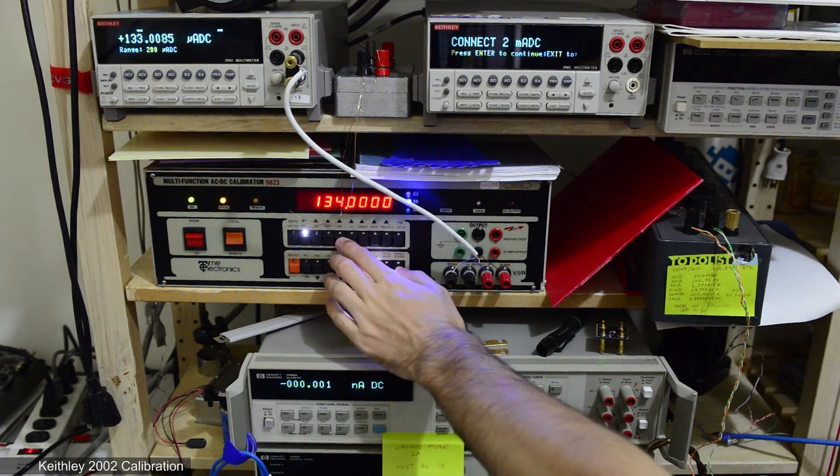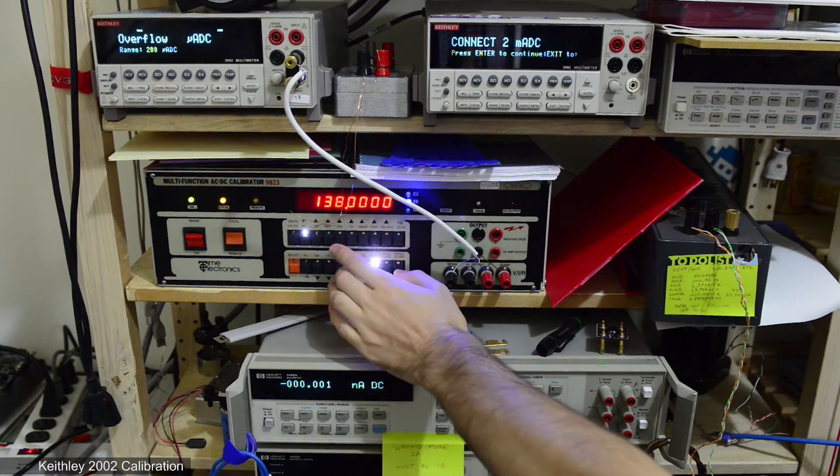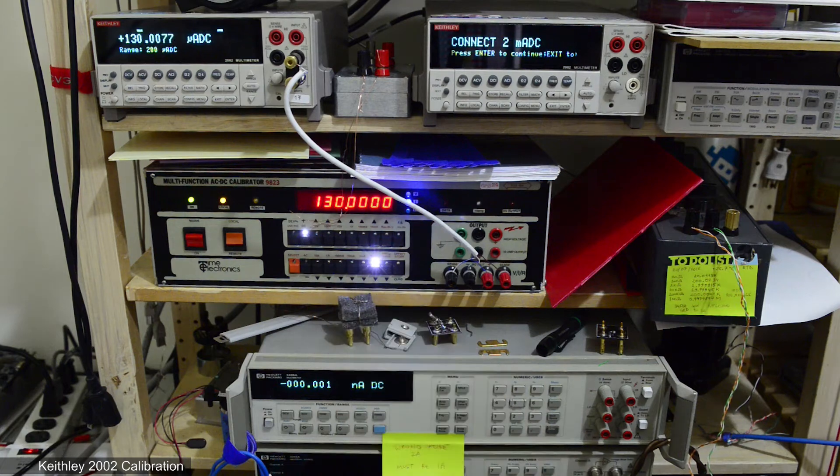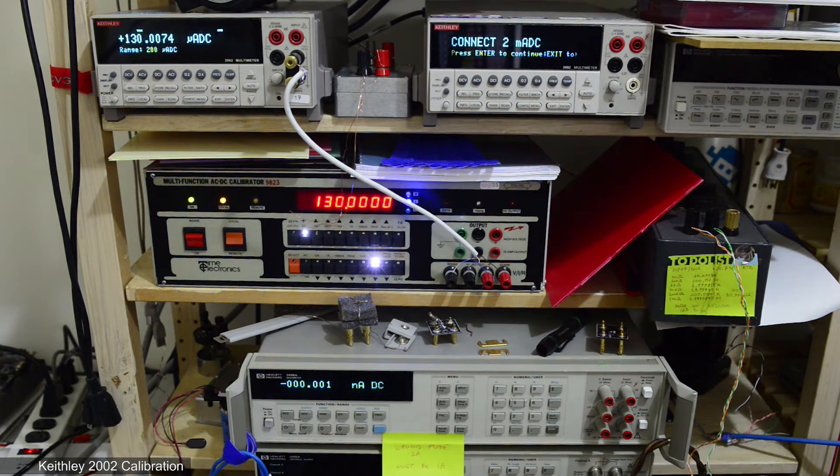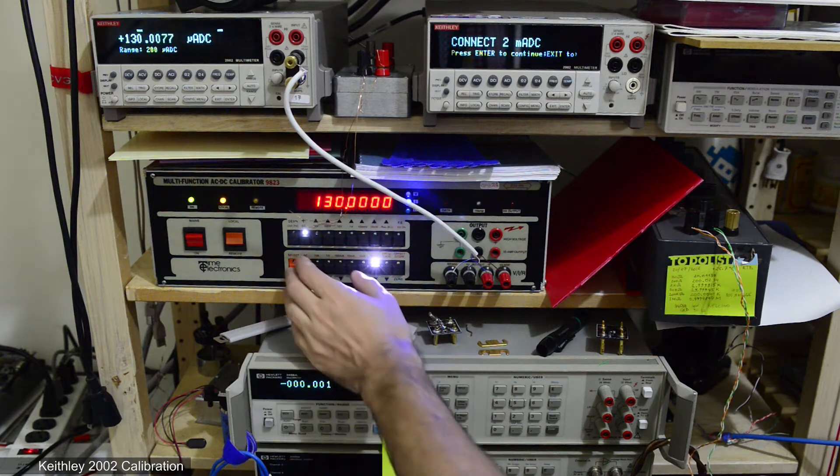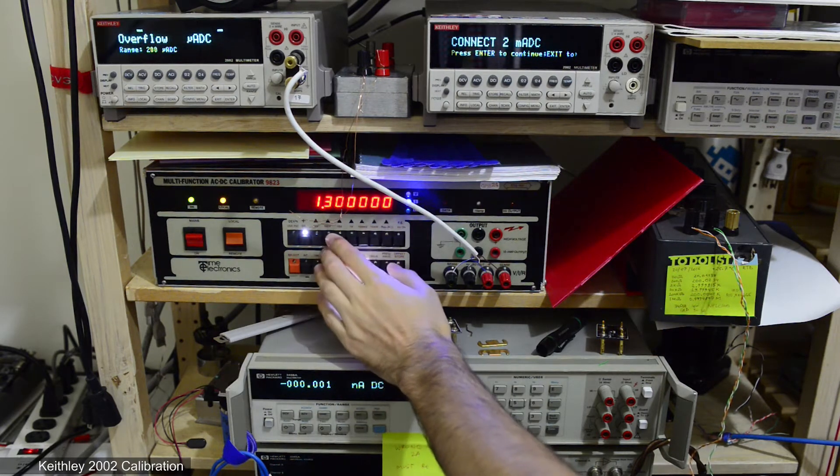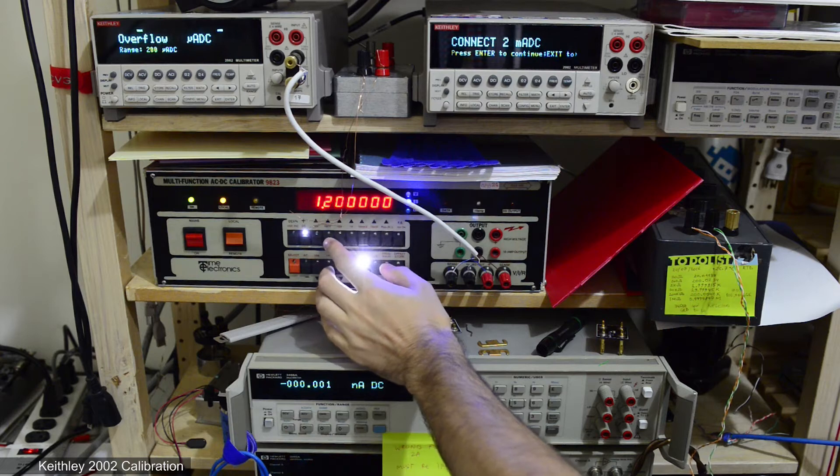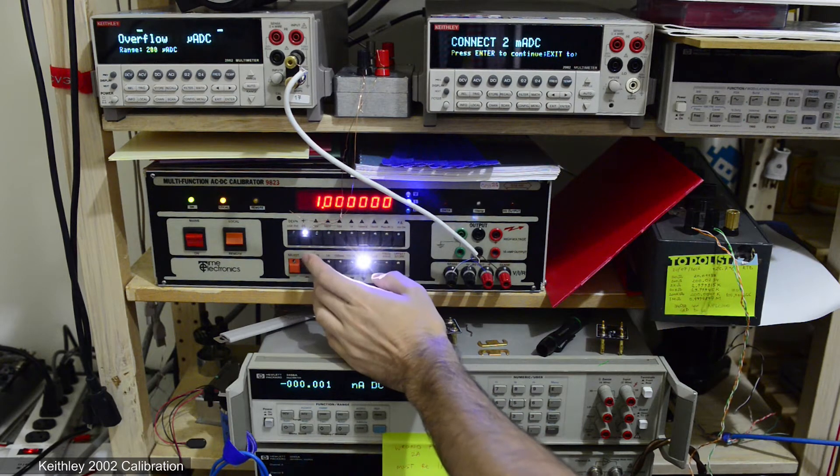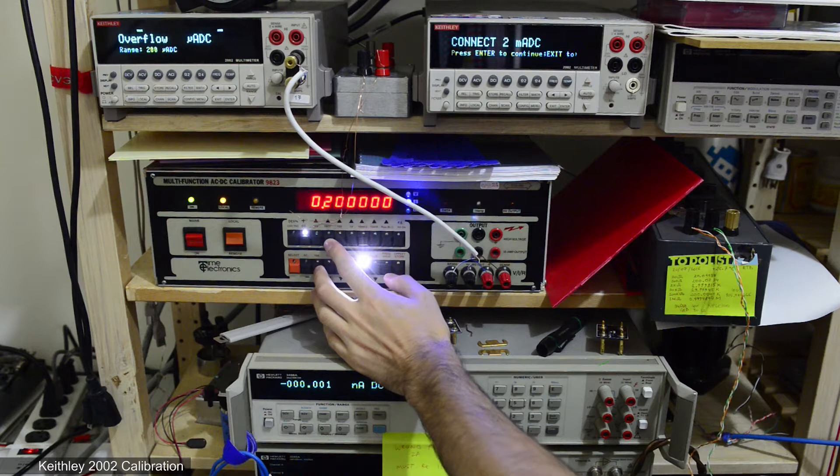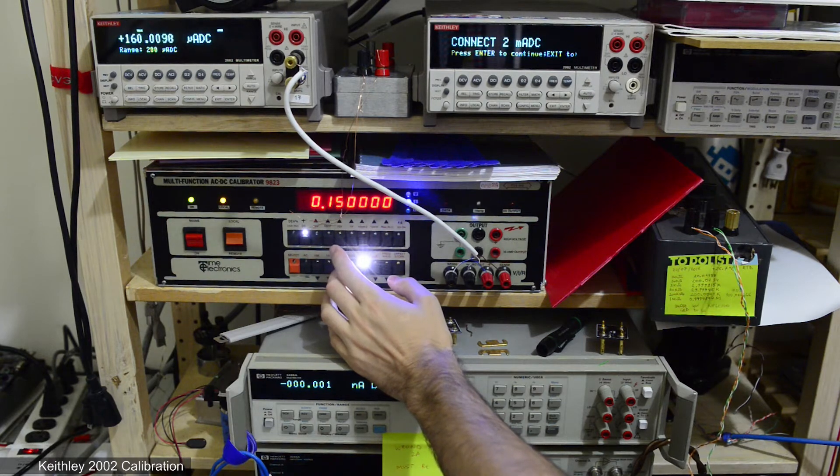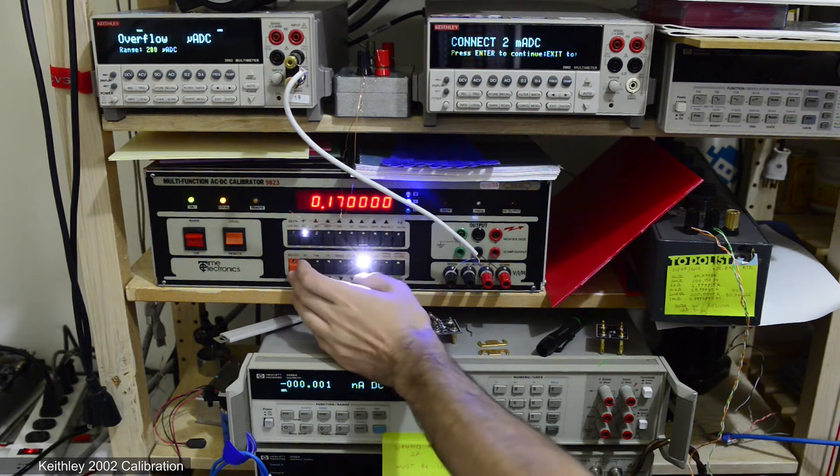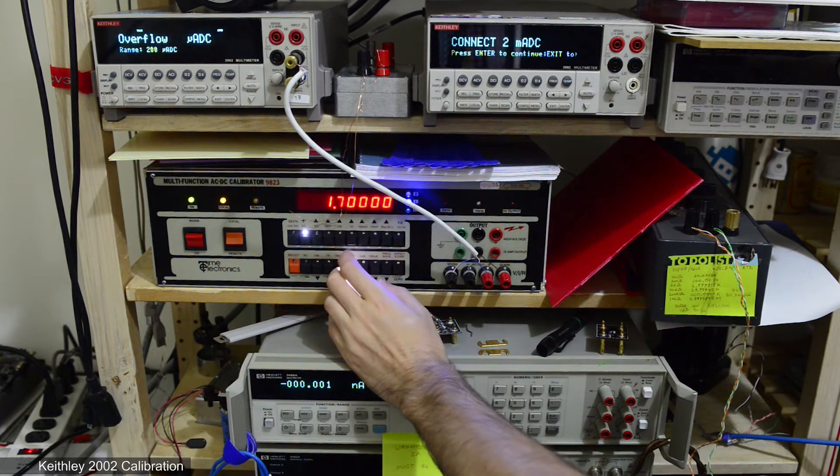So I'll just adjust, yep overflow. Now let's switch calibrator current range to 2 milliamps and see if the problems still exist. 100 microamps, 140, 150, 160 okay around 160 microamps.